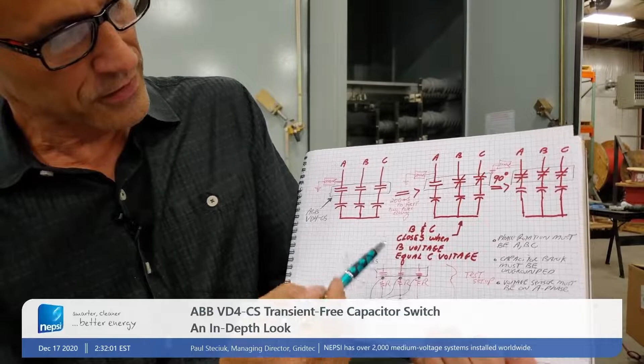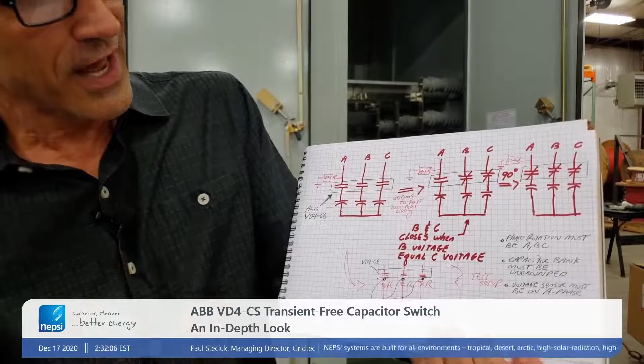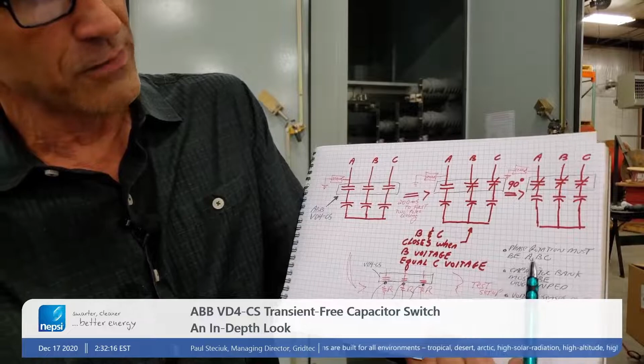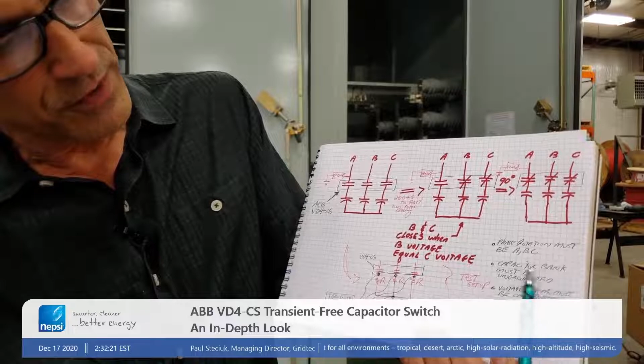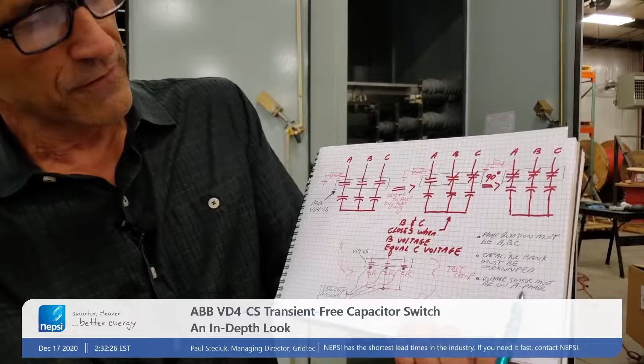And it's very consistent. The closing time from the initiation of the trigger or the close signal to the time that it actually closes is 200 milliseconds. So very consistent operation. One thing about this switching technology you have to remember is that it does require phase A, B, C rotation. The capacitors must be in an ungrounded configuration as we have shown here. And the voltage sensor must be on phase A. And this is how we have it set up.